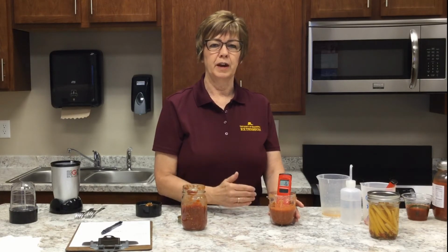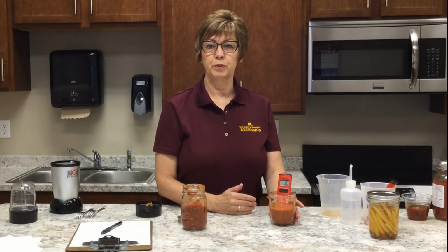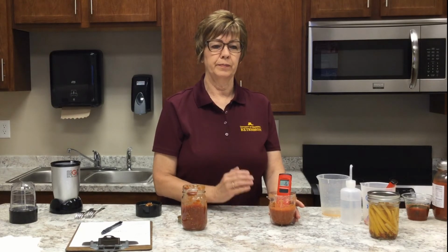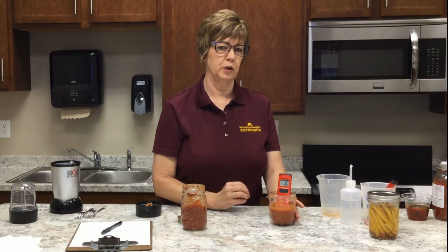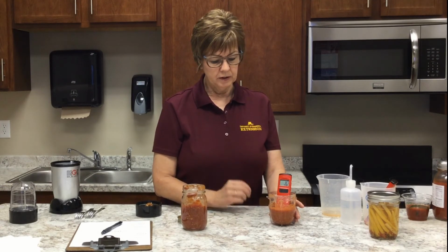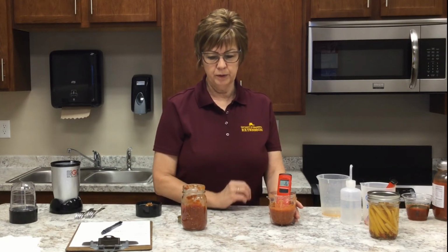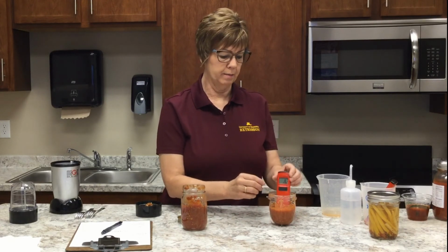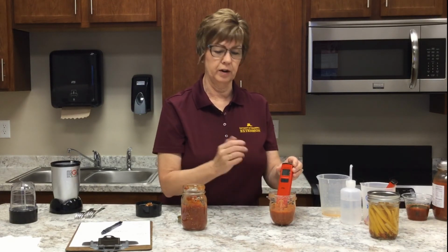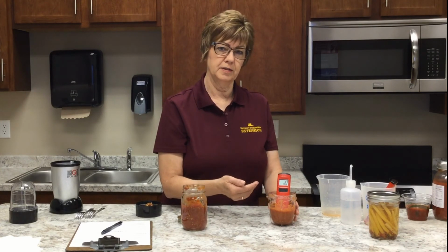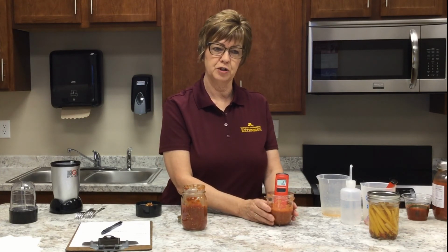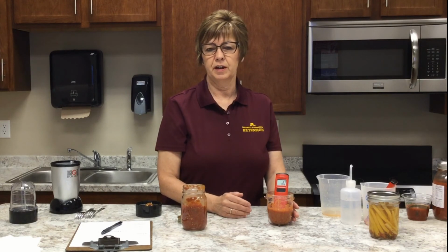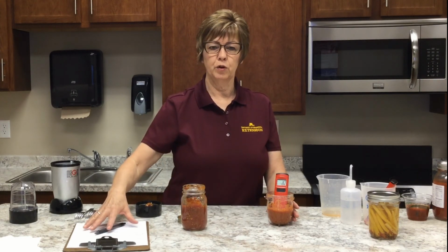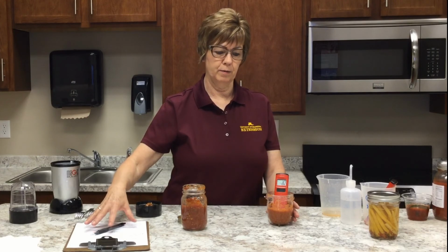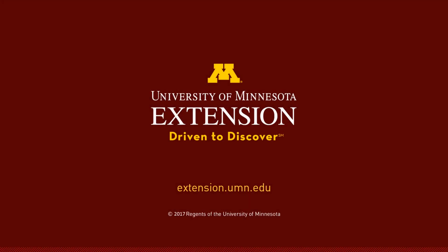So again, that range of equal to or less than 4.6 is what we're striving for, and this is well below that level. So this is acceptable, allowable. What I would do is rinse my probe with distilled water and do a second test using the same batch, but it's our way of getting a second reading. I would make sure I'm recording my results on my record.